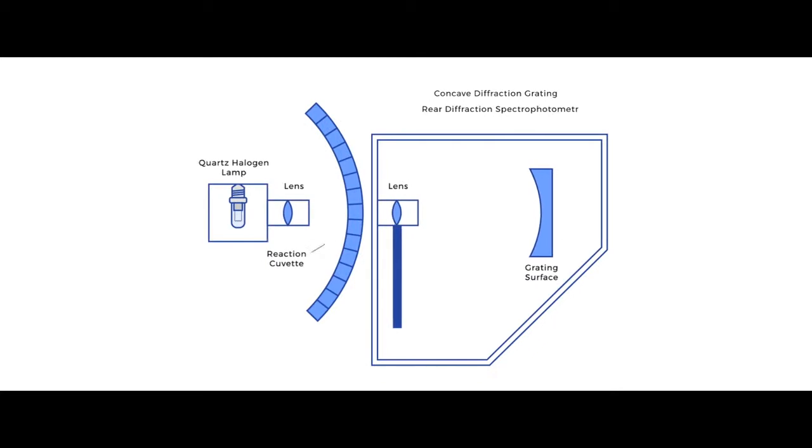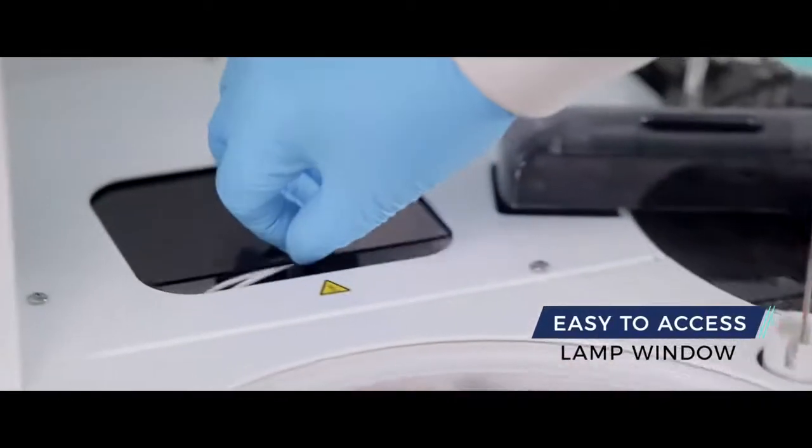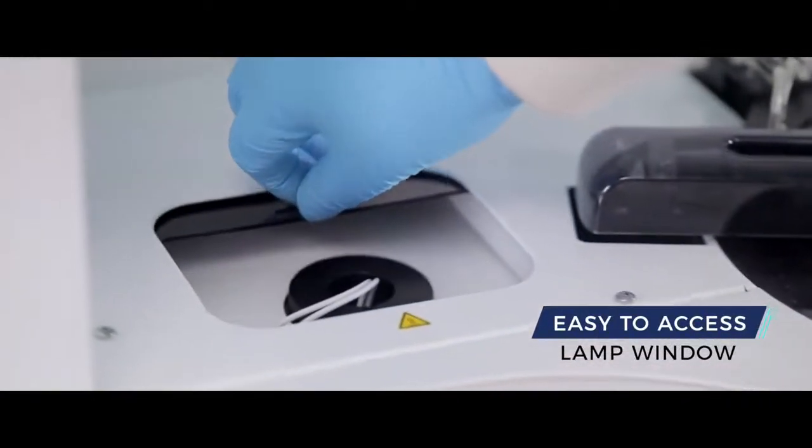The optical system has fiber optic cables that transmit light from the lamp to the cuvette and utilizes grating photometry. 13 wavelengths from 340 nanometers to 800 nanometers are available to accommodate most clinical chemistry testing requirements. An easy to access lamp window is provided for easy maintenance of the system.